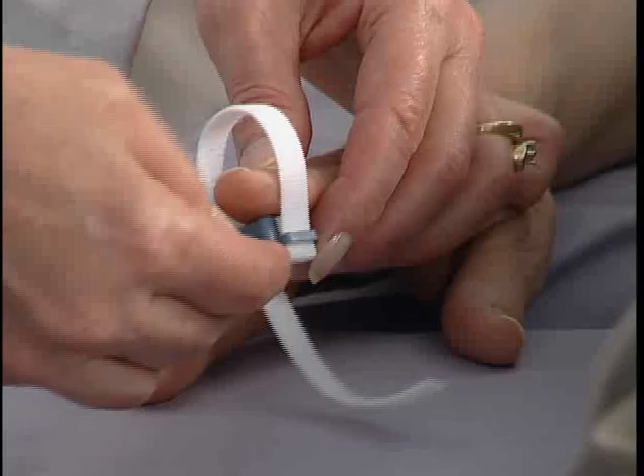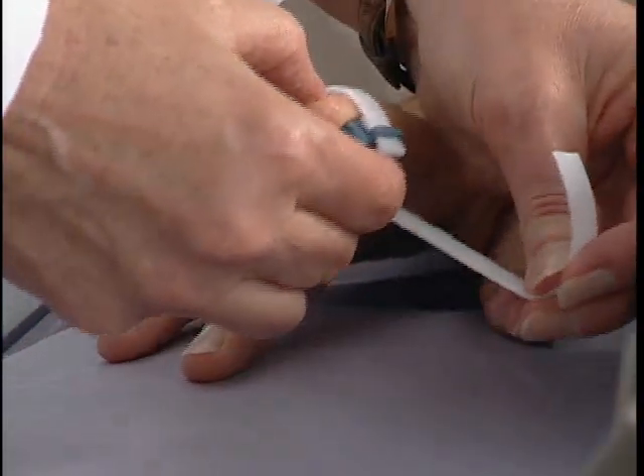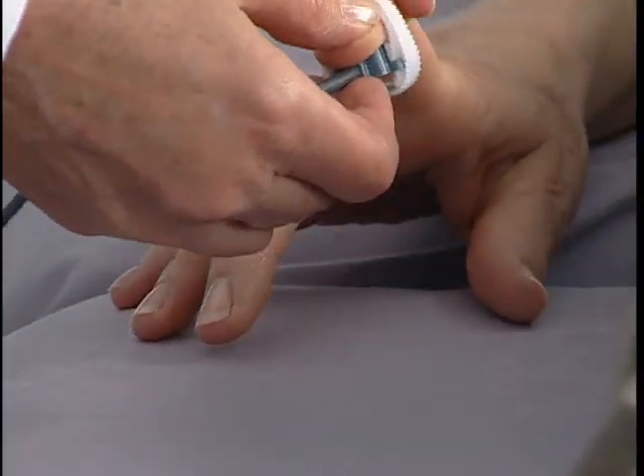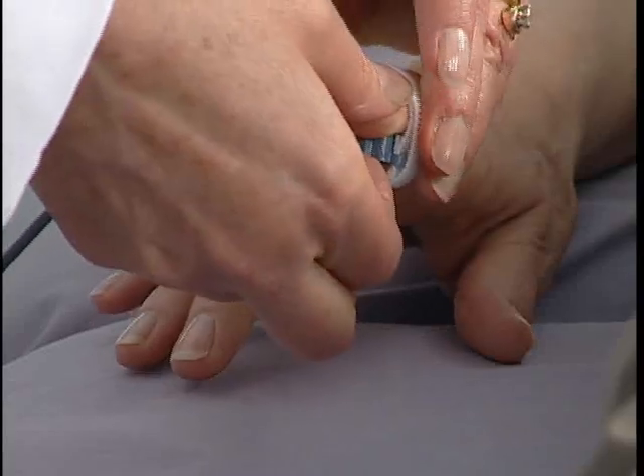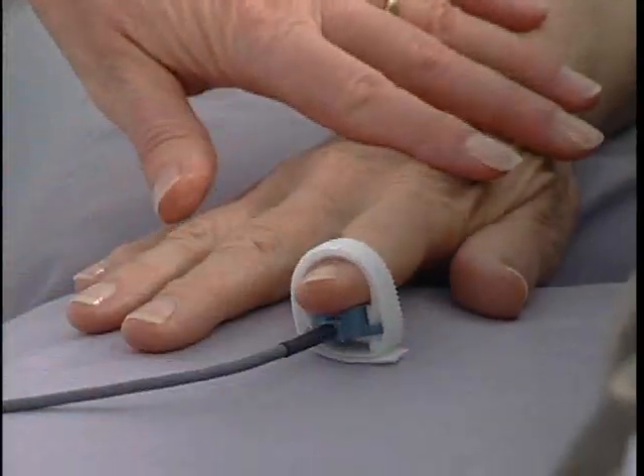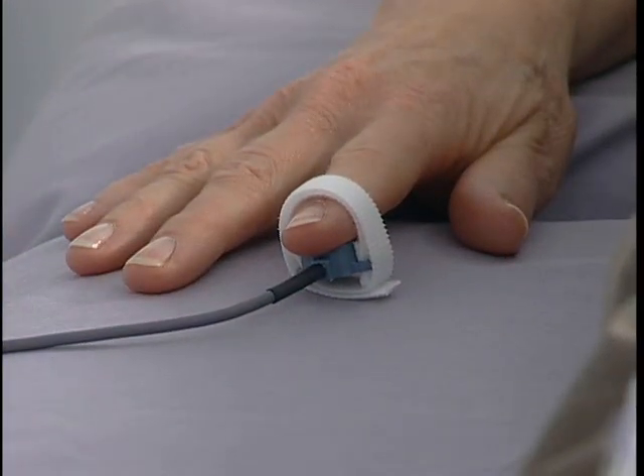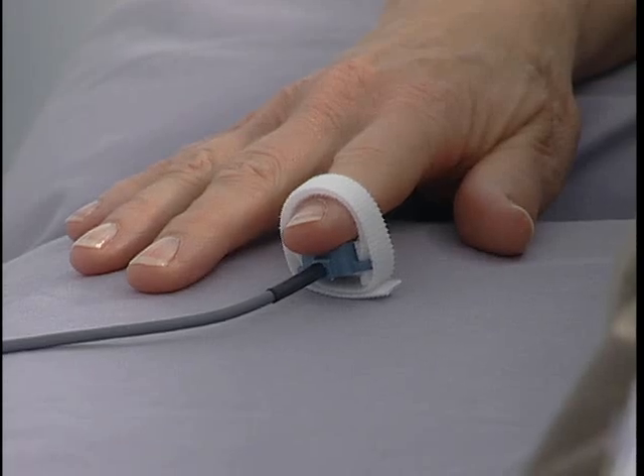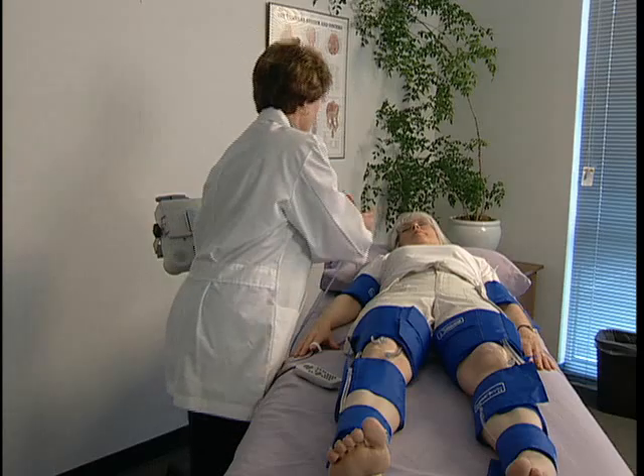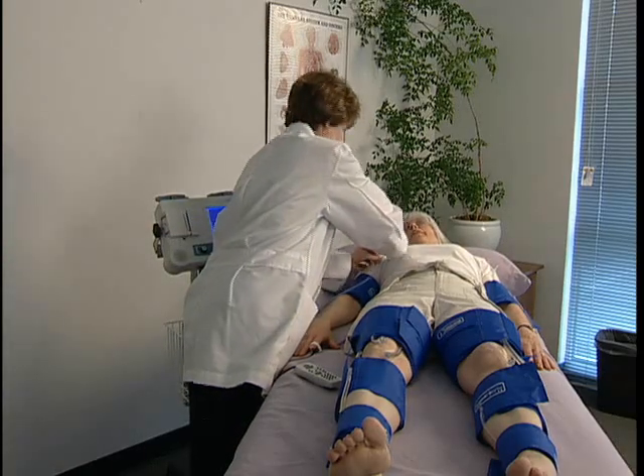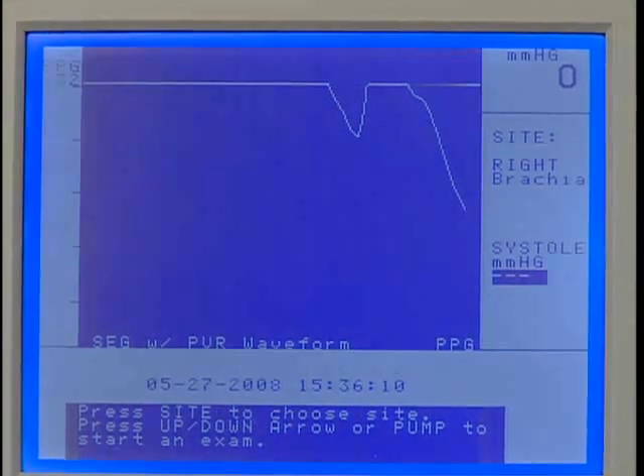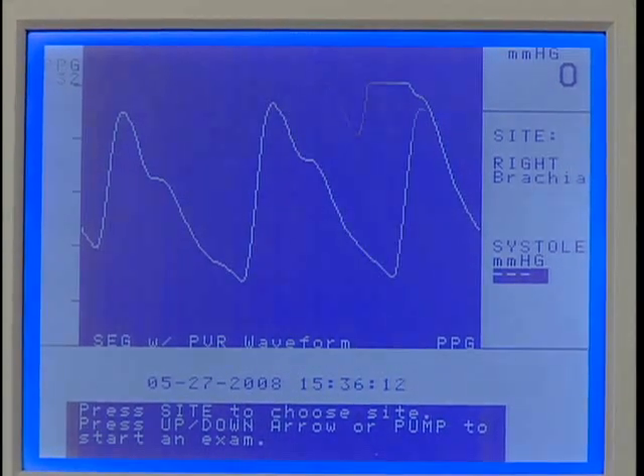Place the PPG probe on the index finger with the blue side of the probe against the skin as shown. The probe should be snug to ensure contact, but not so tight that blood flow is occluded. The patient must be still to acquire a PPG signal. Start at the right brachial and connect the hose to the cuff. Wait a few seconds for the waveform to stabilize after applying the probe.